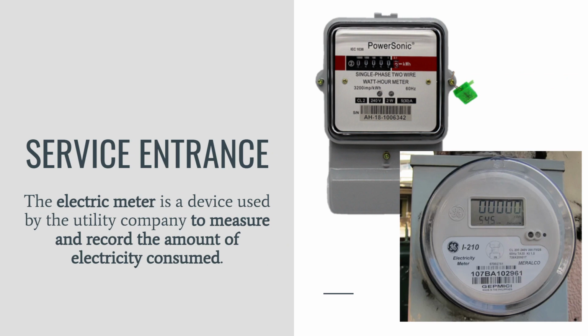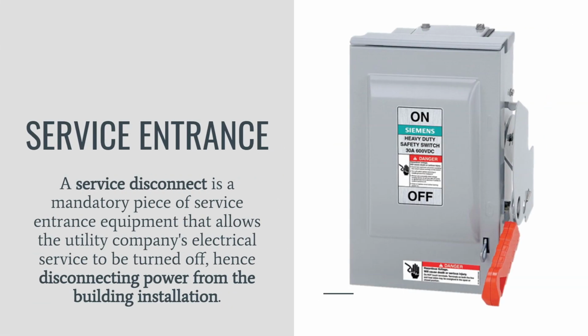power utilized in kilowatt-hours. Metering used for services rated above 400 ampere is done with a current transformer or CT. CT devices measure the current flowing through each ungrounded or hot conductor. CT metering devices are contained in a CT cabinet, which is part of the service entrance equipment. A service disconnect is a mandatory piece of service entrance equipment that allows the utility company's electrical service to be turned off, hence disconnecting power from the building installation. The service entry conductors are protected by a set of fuses or a circuit breaker.